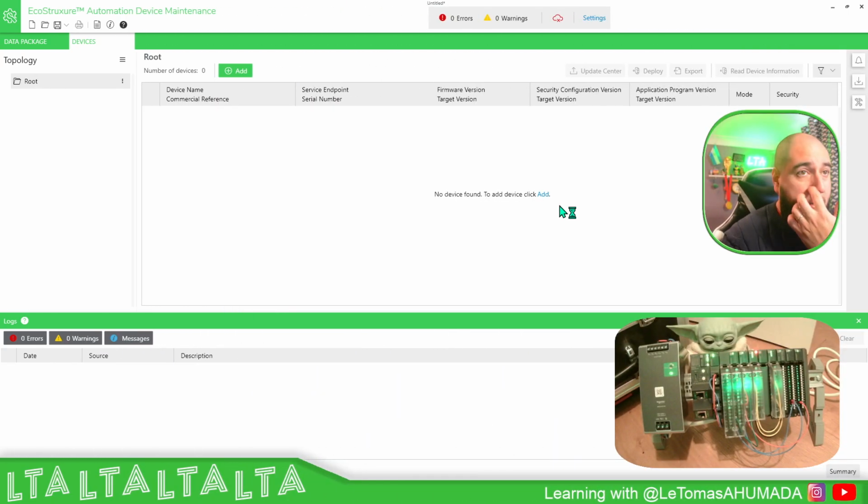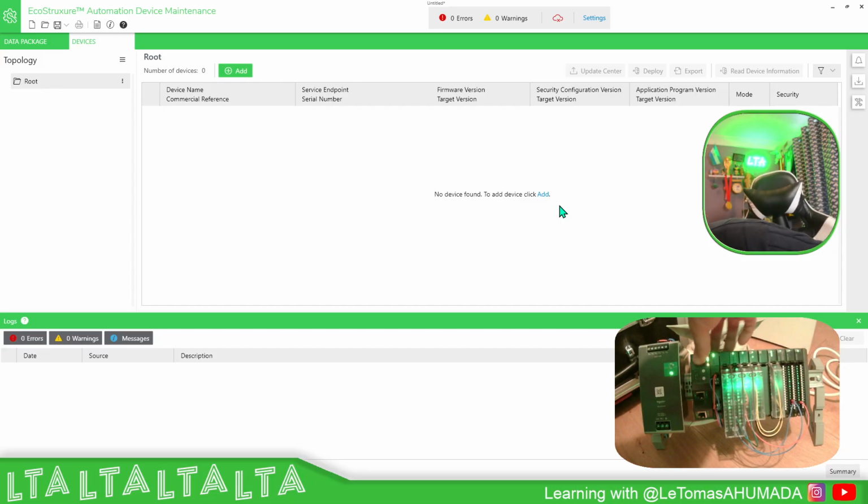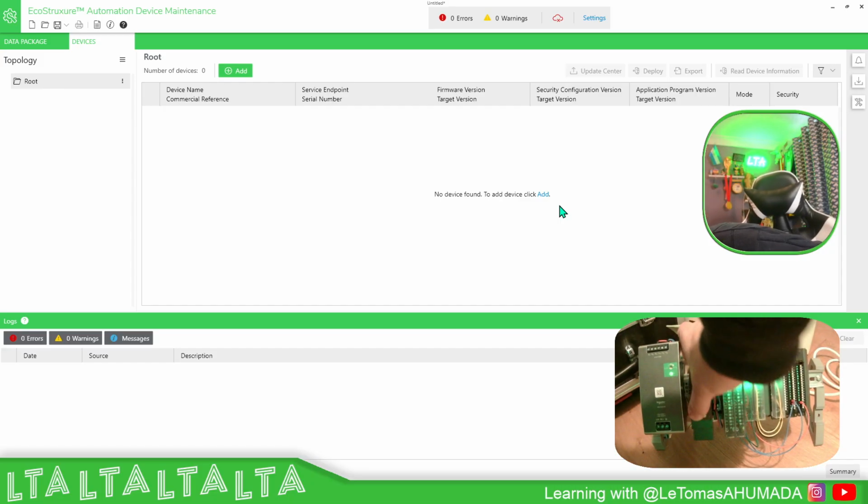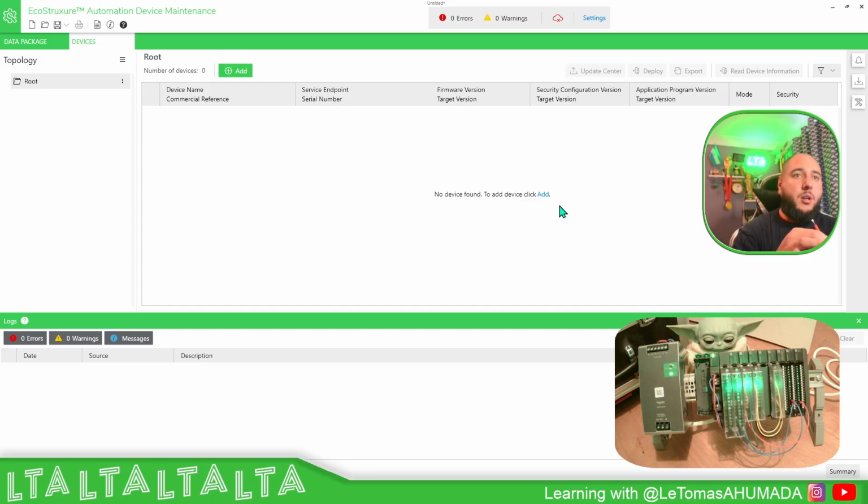What I'm going to do basically would be to power cycle it. No, I'm going to factory reset. To find a screw. And now I'm going to make the factory reset so we can connect to a new one. In the back part of the EdgeIO, we have a rotary switch. The rotary switch needs to point to the north. Okay, it's pointing to the north.